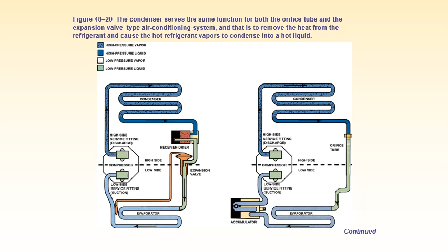Now another important thing is the broken lines. The condenser is connected to the expansion valve or the orifice tube using aluminum fittings. Sometimes there is a breakage of these aluminum fittings because aluminum is rigid, it is not flexible, and it breaks by certain shocks or vibrations. So you have to locate these fittings where there is a leakage. You have to repair the leakage.